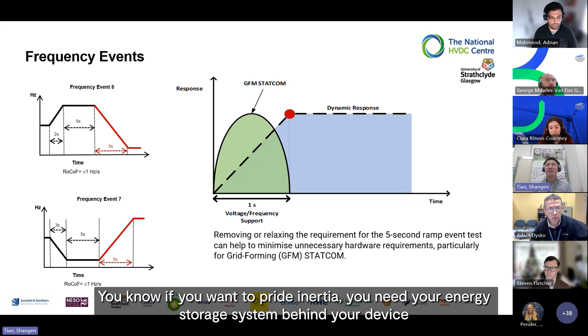Back to this 5-second testing event: after our testing, we may suggest removing or relaxing this 5-second ramp event, because it can help minimize unnecessary hardware requirements, especially for the grid-forming STATCOM with energy storage. If you want to provide inertia, you need an energy storage system behind your device.